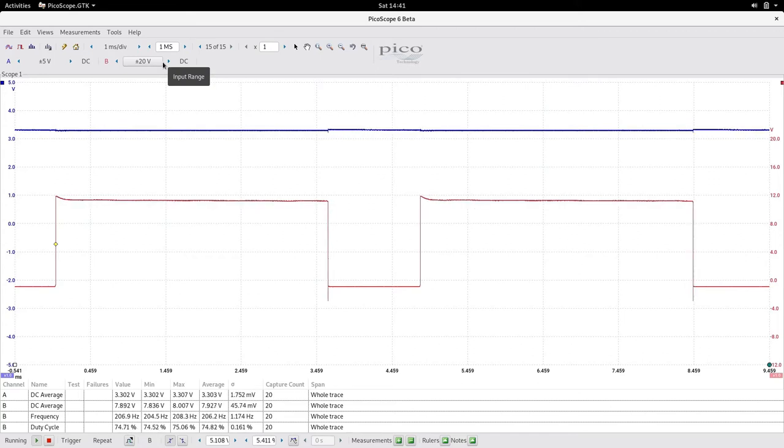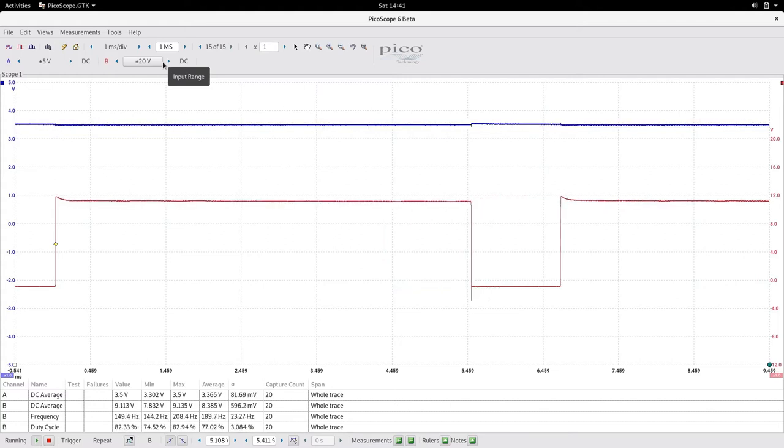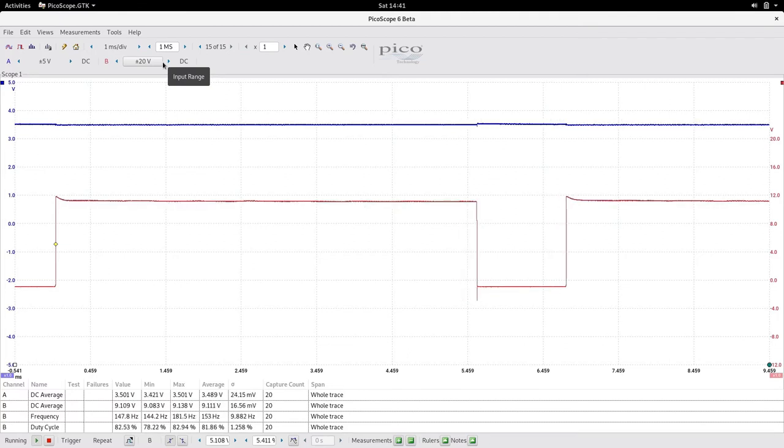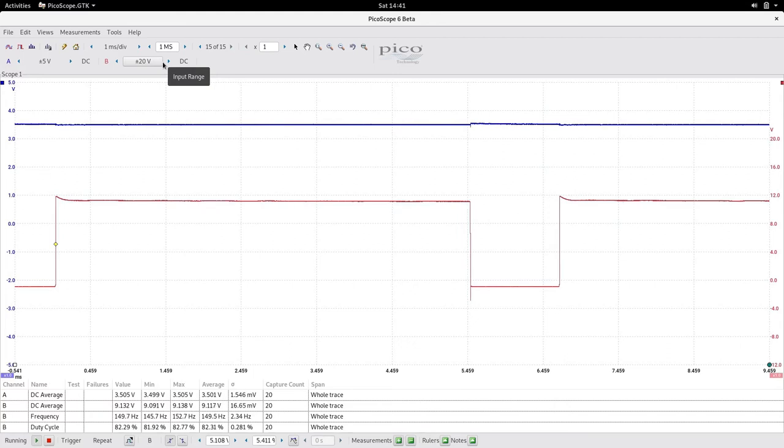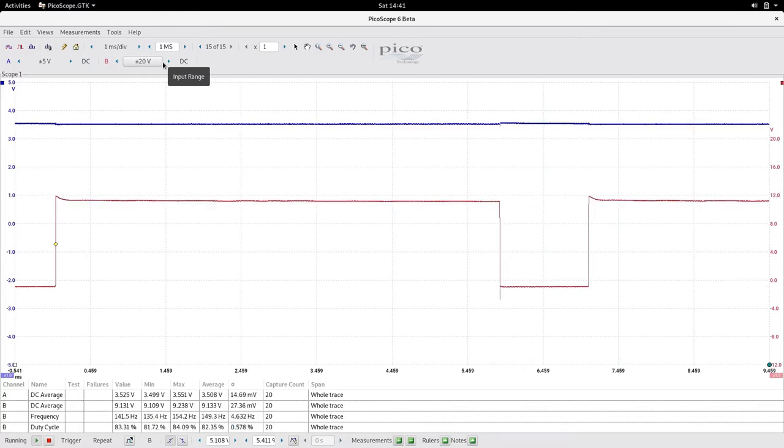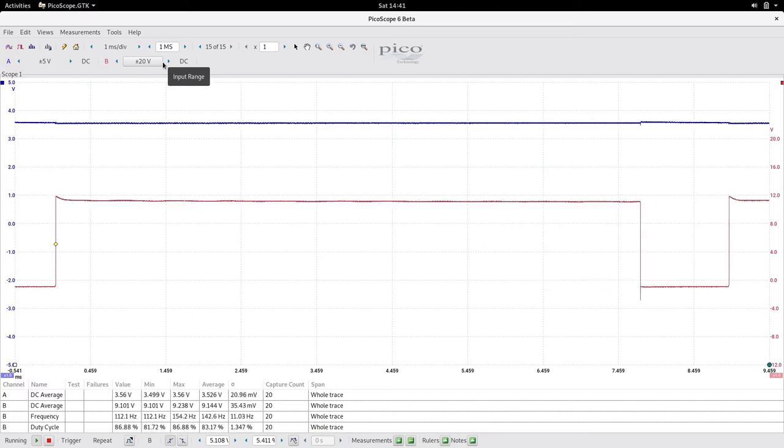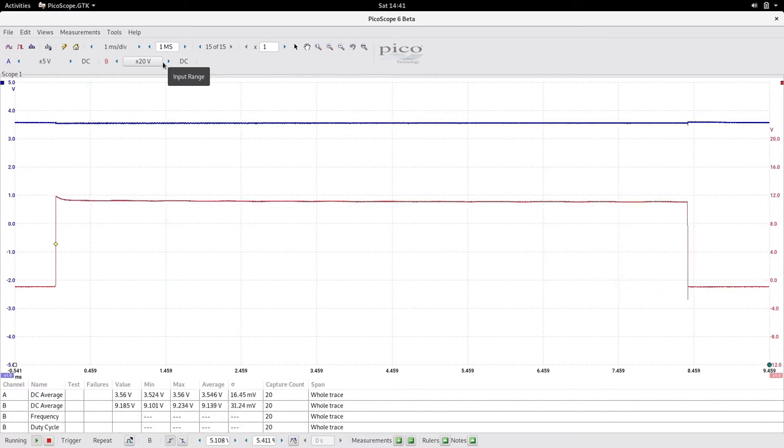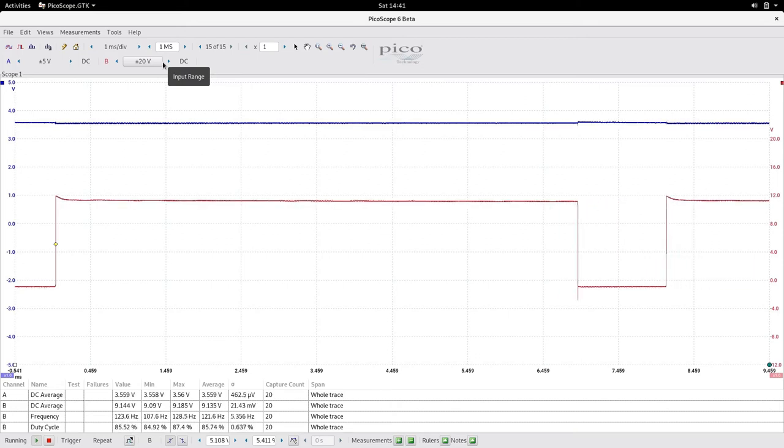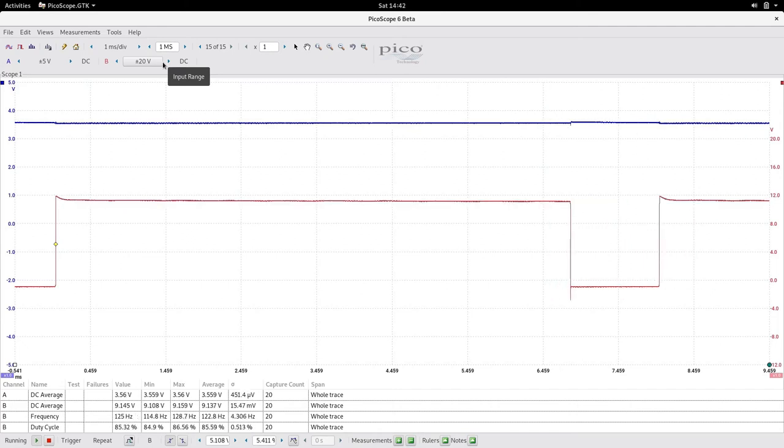It seems to fluctuate between 74, 75. I must have moved it at that point in time up to 80. At 80 percent, yeah that is erratic. It's not the control unit because you can see the blue line, the voltage is more or less stable there, but the red line is all over the place. That is obviously affecting the output of that conveyor belt as was reported by the operator, so there's an issue there.